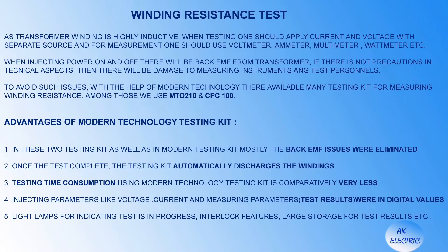To avoid such issues, with the help of modern technology there are many testing kits available for measuring winding resistance. Among those, we use MTO210 and CPC100. In these and other modern testing kits, the back EMF issue is largely eliminated — once the test is complete, the testing kit automatically discharges the windings. Testing time using modern technology kits is comparatively very less. Injecting parameters like voltage and current, and measuring parameters, are in digital values. Light lamps for indicating test in progress, interlock features, and large storage for test results are added advantages.